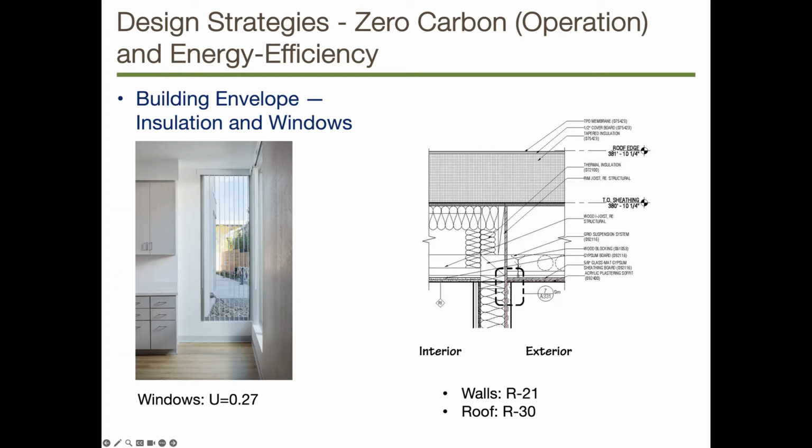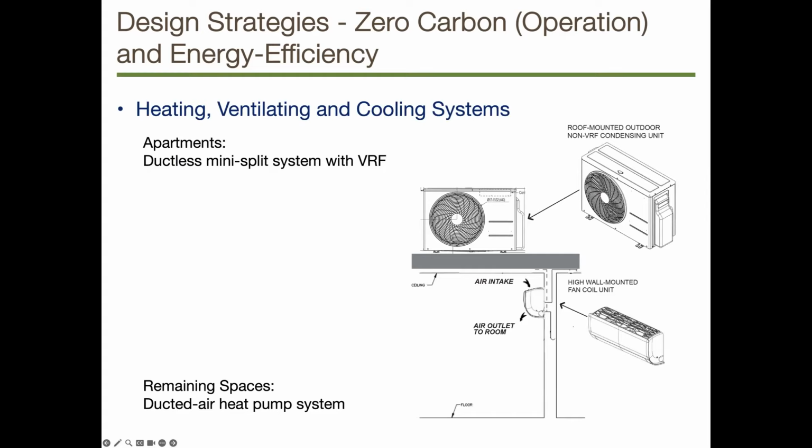And this is the HVAC system. Since there's no gas, it's going to use a heat pump in one way or another. This one has a heat pump for each unit, and the condenser part is located on the roof, and then refrigerant piping comes down to the fan coil unit. Since it's a studio, it makes it very simple for the fan coil unit to heat or cool the space. And the main attribute is they didn't have to bring ducts into the units.